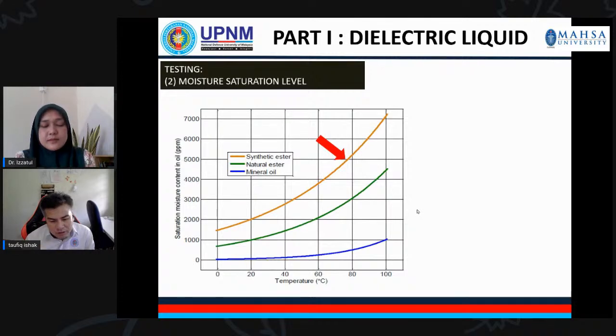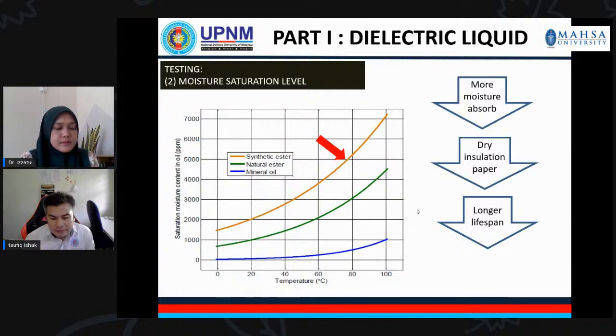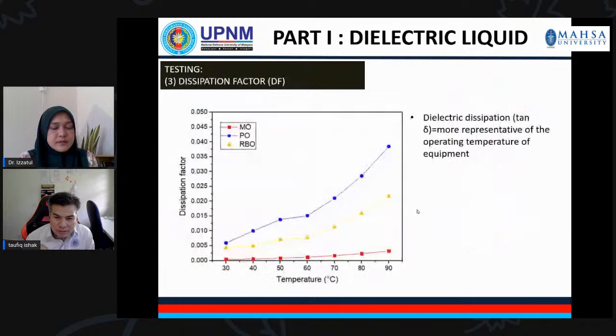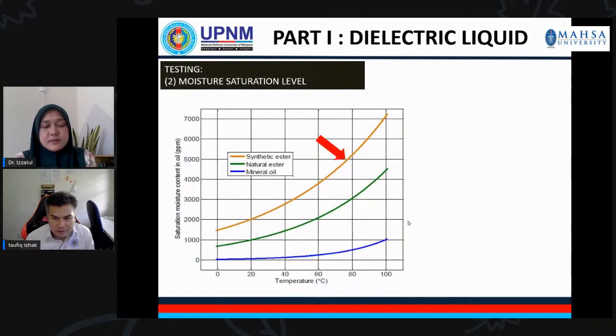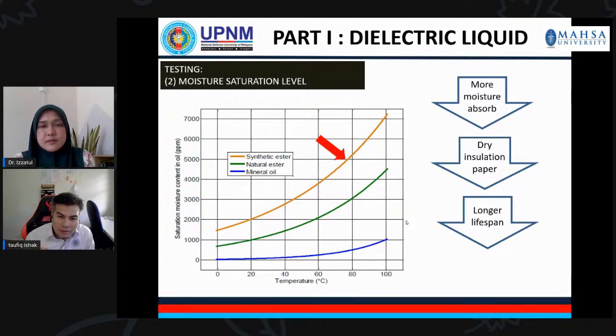That's why we can say that one of the important parameters in oil moisture measurement is related to the water solubility, or we can say the water saturation level inside the oil. When the moisture in the oil exceeds the solubility for that temperature, it will produce free water inside the oil. When you have free water inside the oil, it becomes a conductive part inside the insulation material, in which it can make voltage breakdown happen easily.